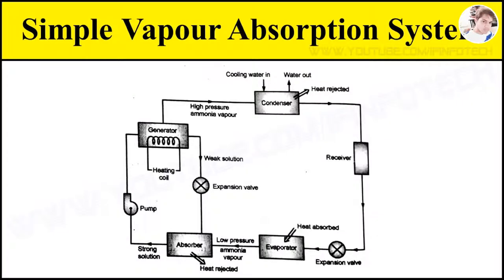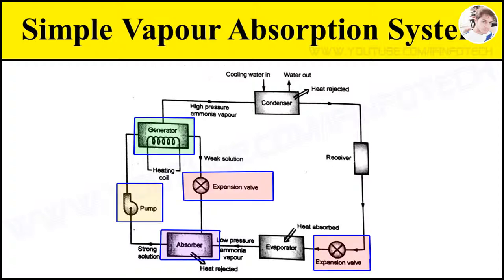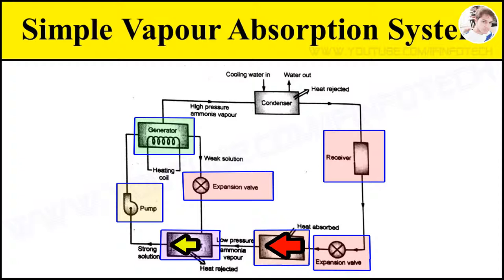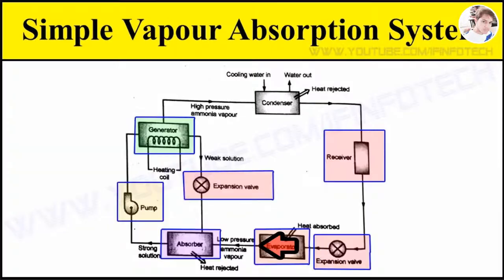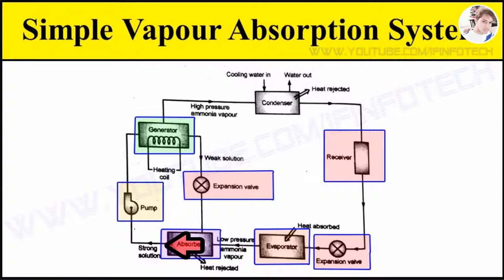This figure shows a simple vapor absorption system which consists of an absorber, pump, generator, expansion valve, evaporator, and receiver. The working fluid is an aqua-ammonia solution, where ammonia acts as the refrigerant and water acts as the absorbent. In this system, the low-pressure ammonia vapor leaving the evaporator enters the absorber.